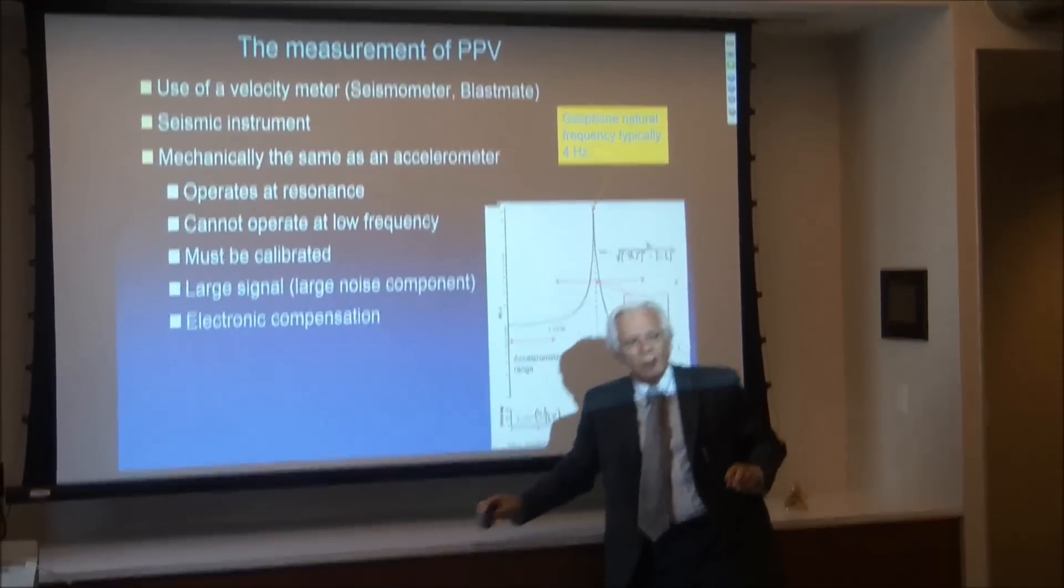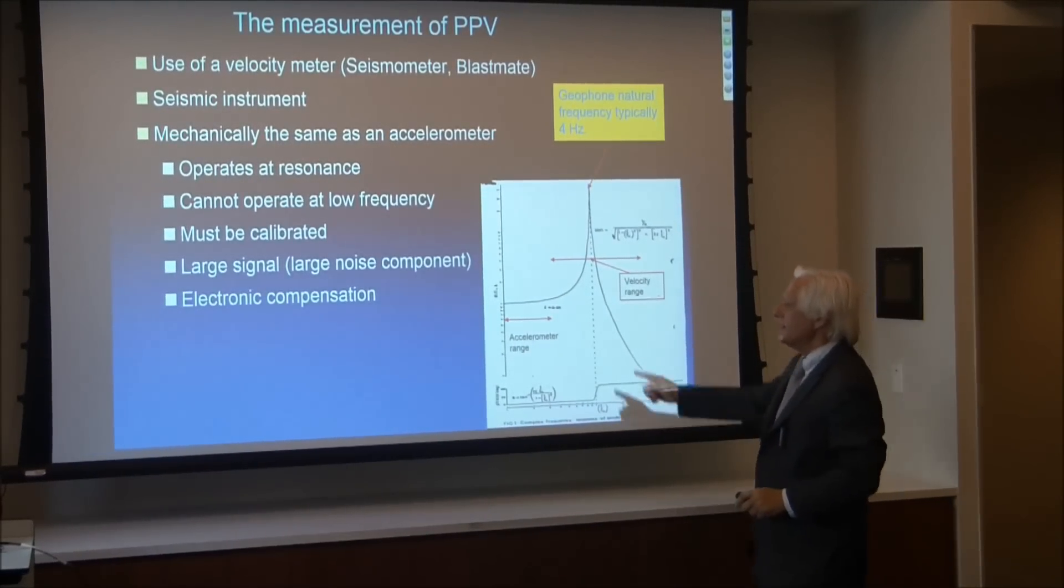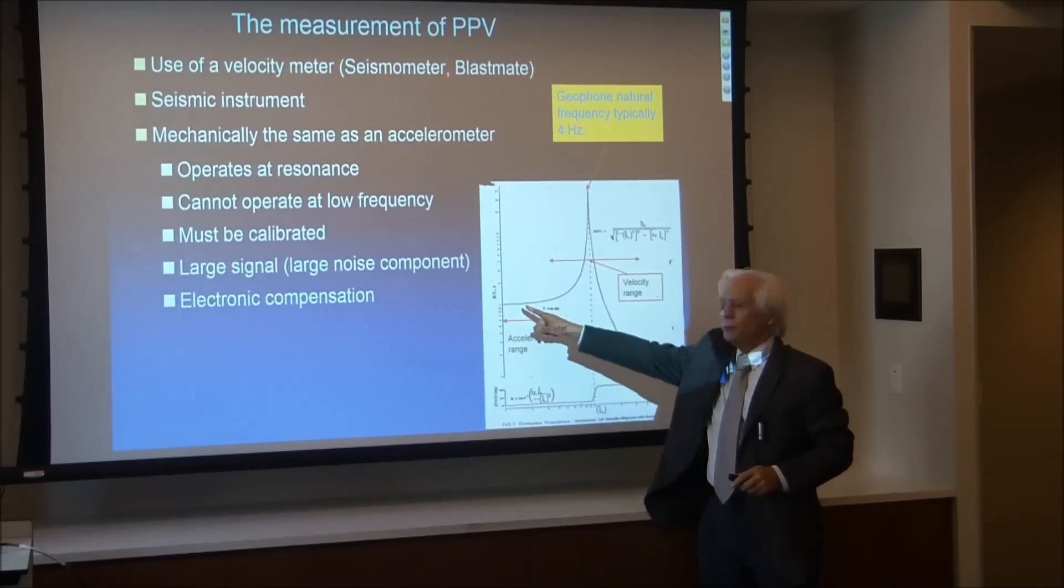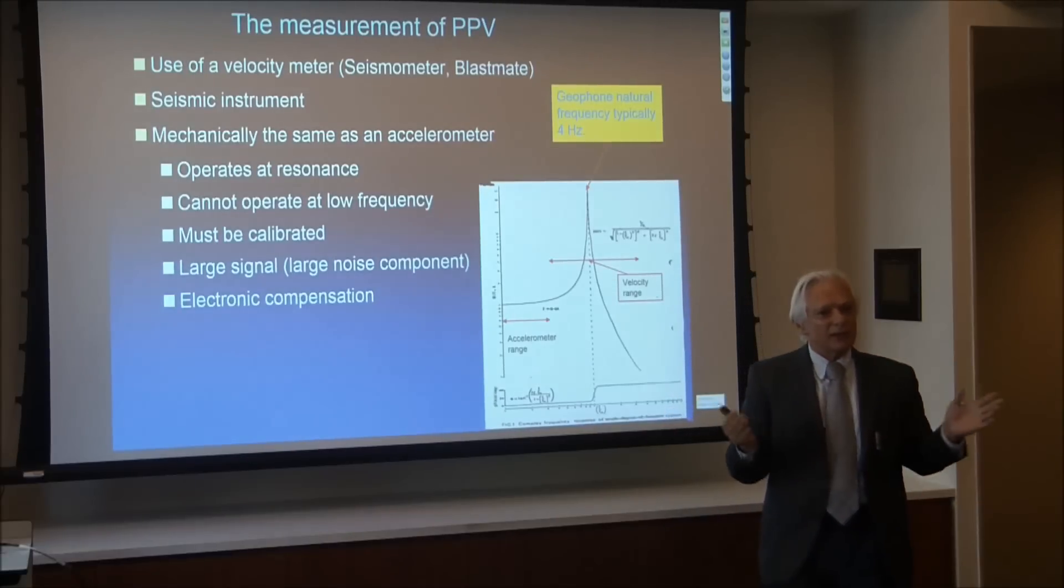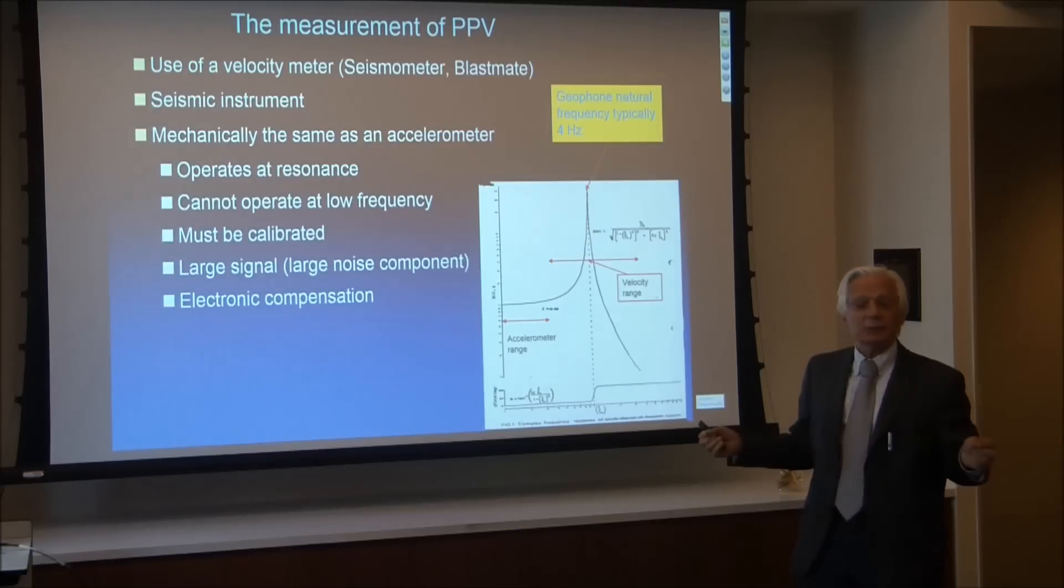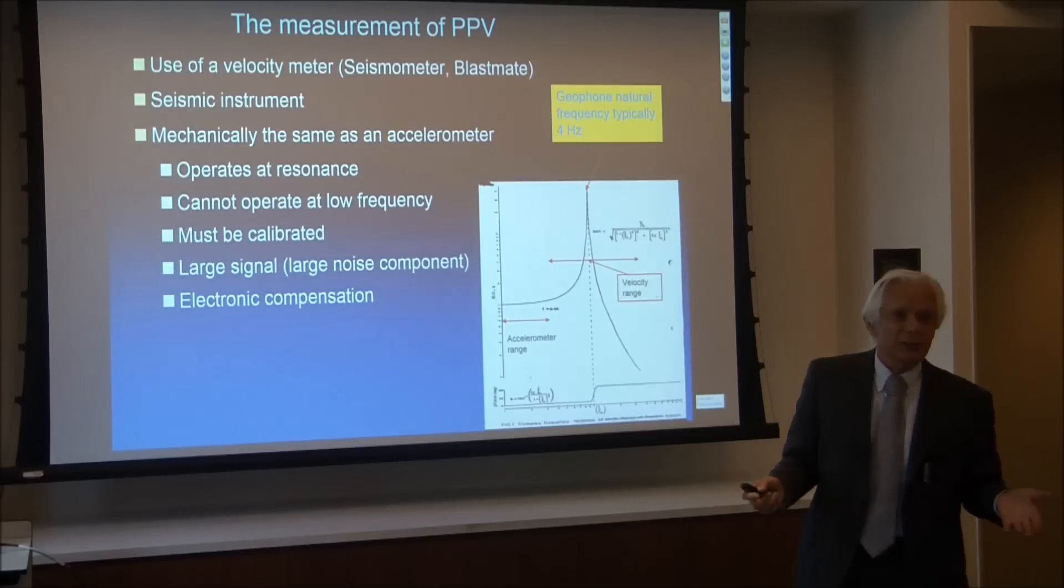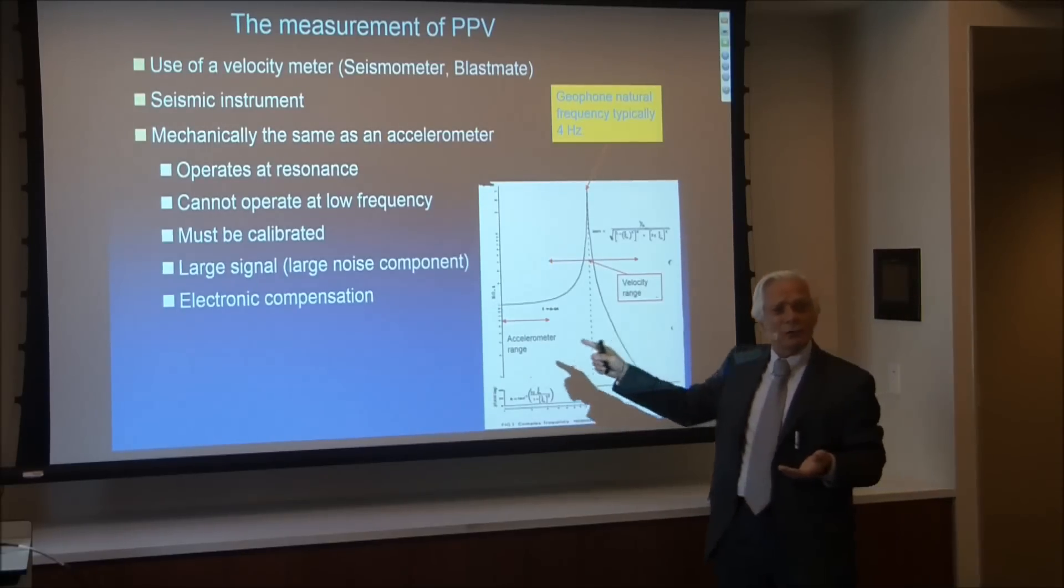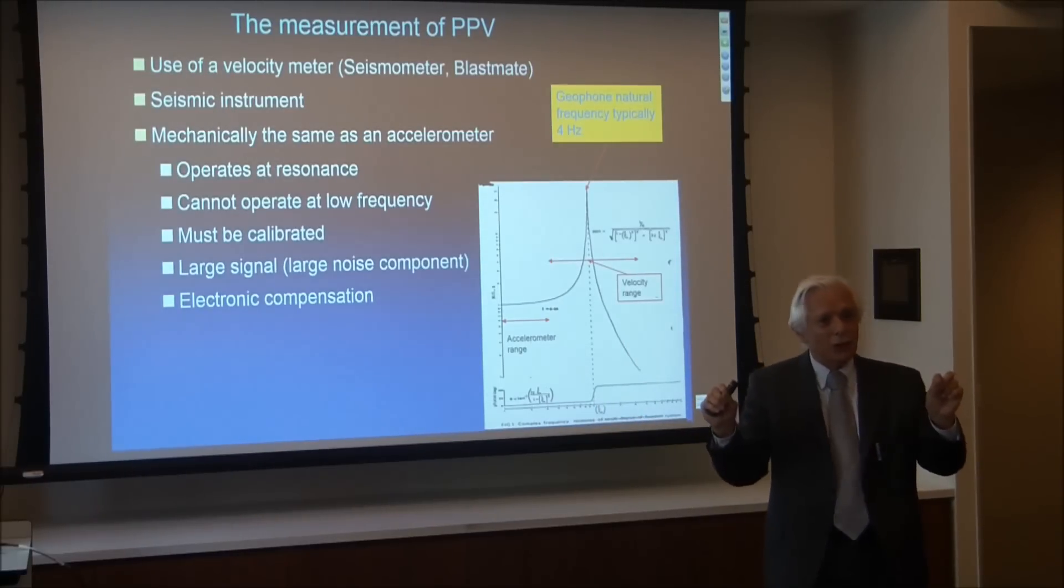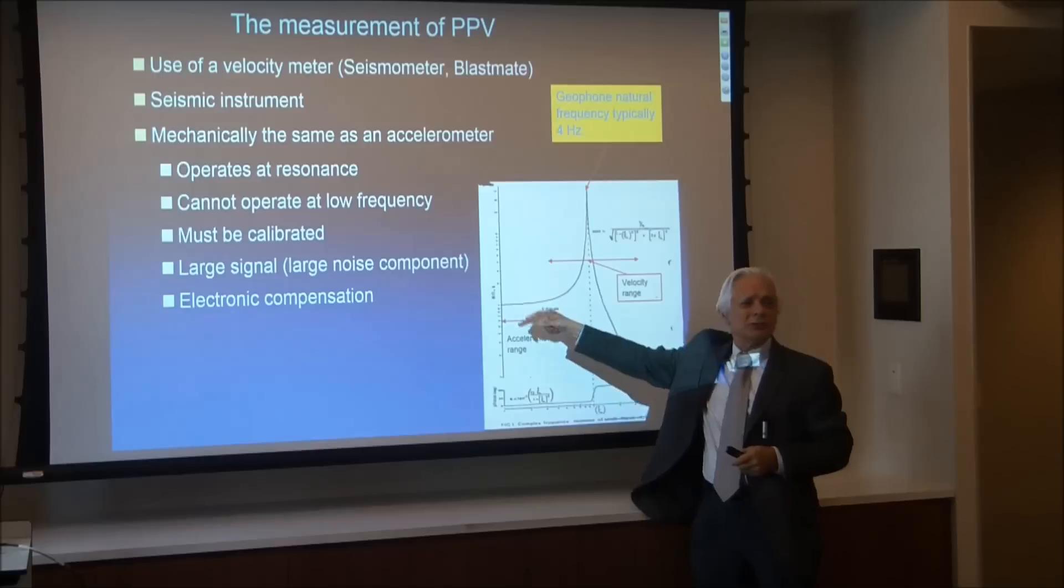All seismic instruments depend on this principle. So what we have here is in this low frequency range, that's where accelerometers work. And you'll see that it's a pretty flat characteristic. So accelerometers now are our preferred instruments because they work all the way down to zero frequency. And because gravity is always there, they don't even switch it off at weekends. Accelerometers will respond to tilt as well, so they measure not just acceleration but tilt as well, which is acceleration at very close to zero frequency.